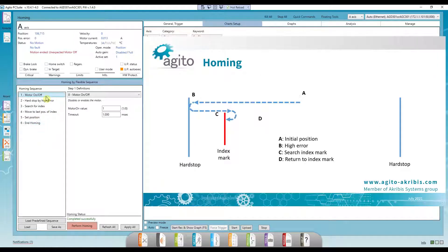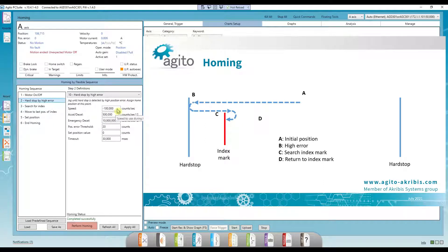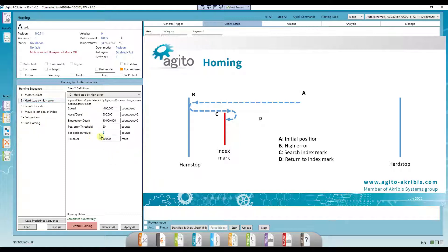First, the motor is turned on. Then we send the motor in the negative direction until the position error passes a certain threshold. Make sure to use a suitable speed. We don't want to hit the hard stop too strongly. At that point, we set the position to 0. The timeout is set to 30,000. This step must finish in less than 30 seconds.